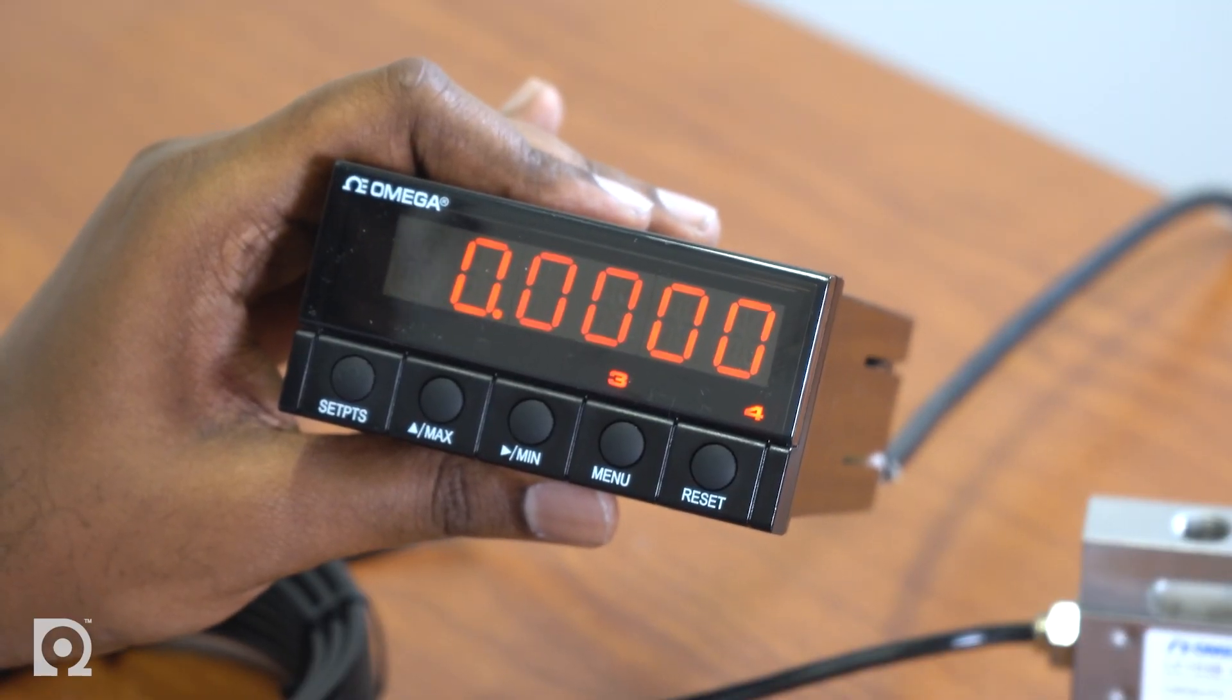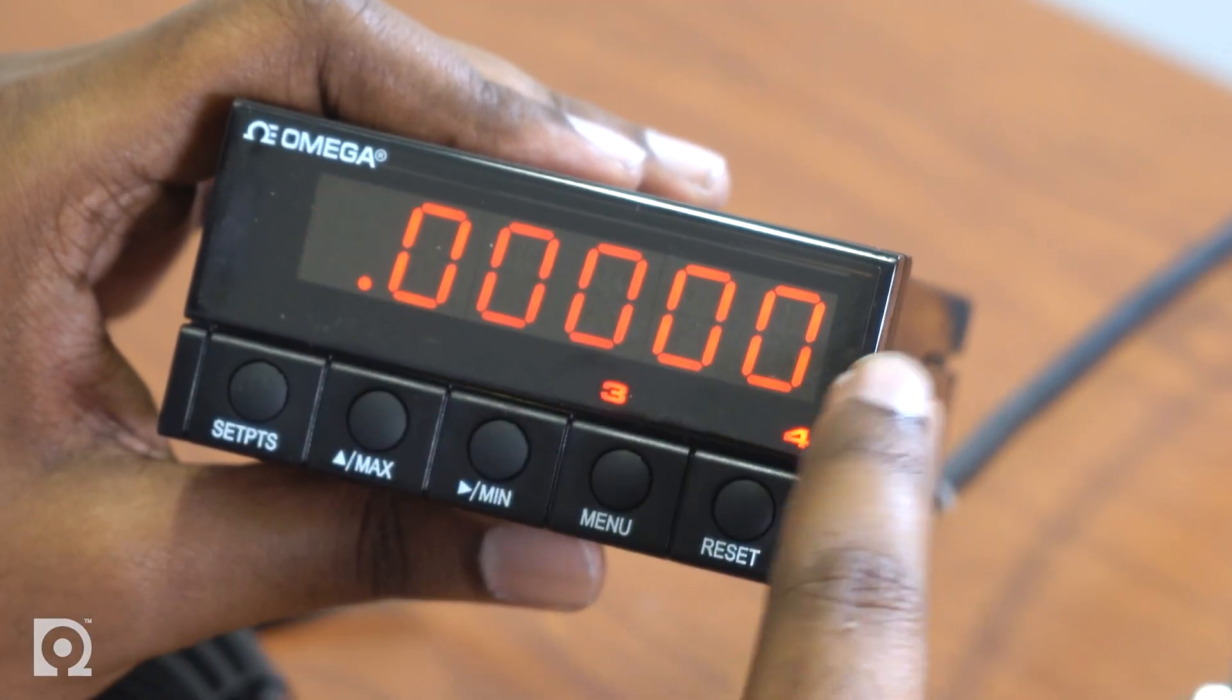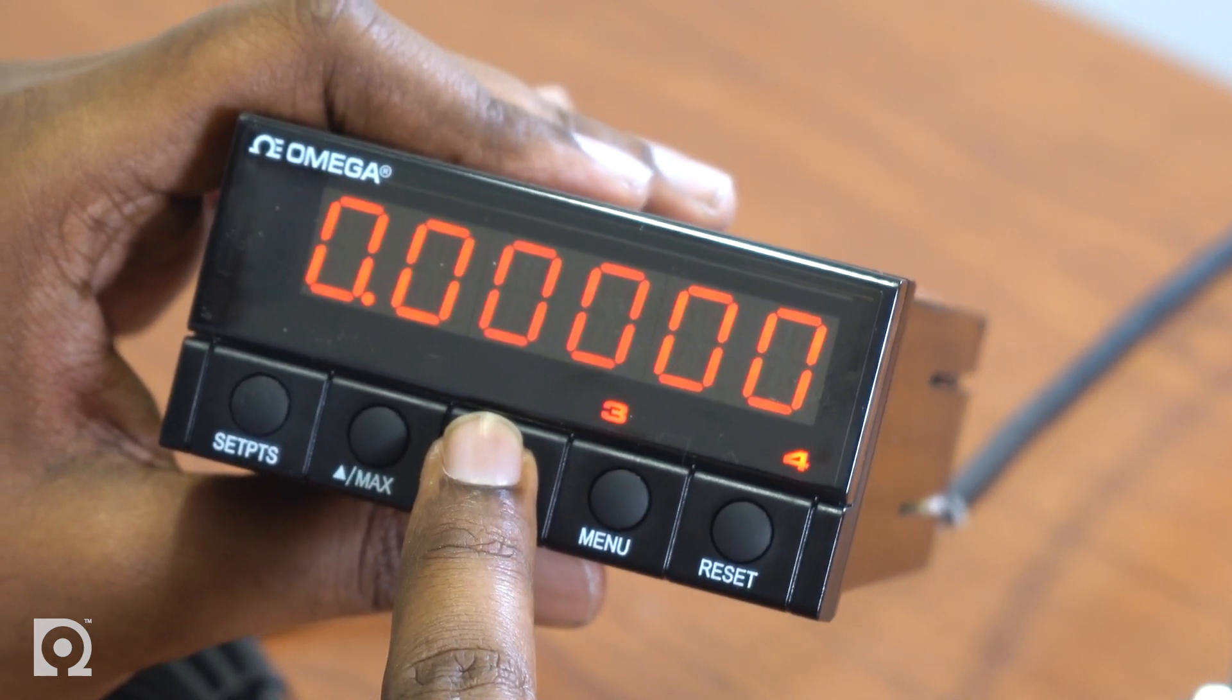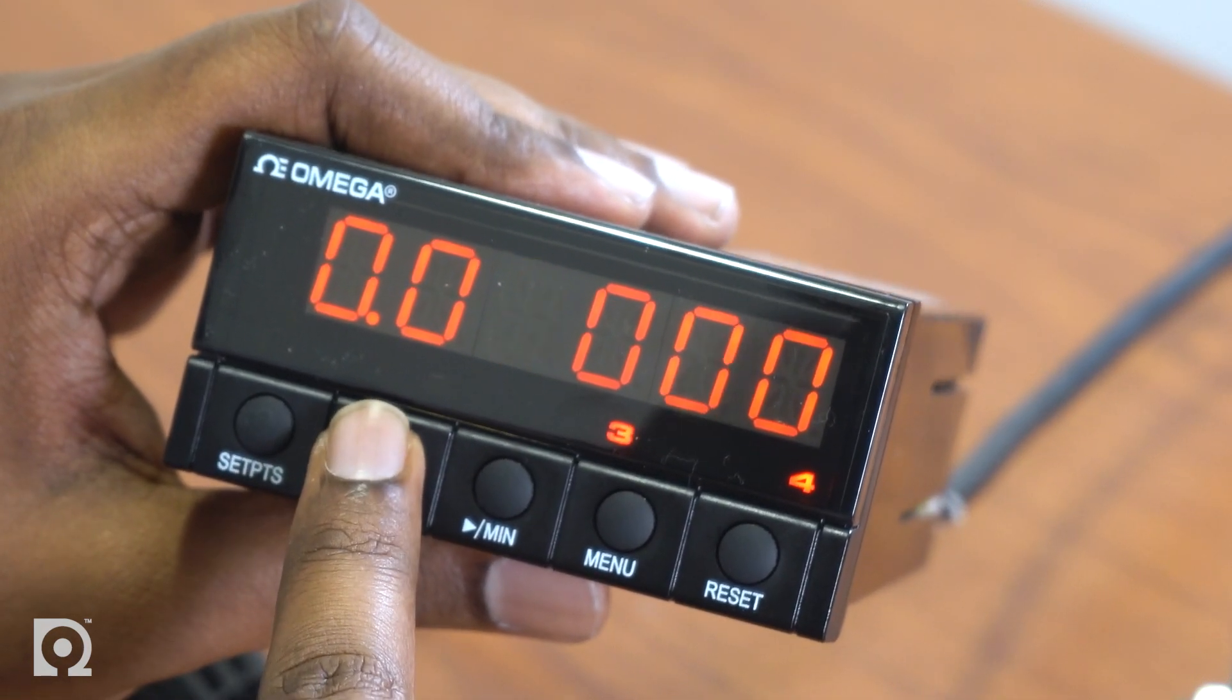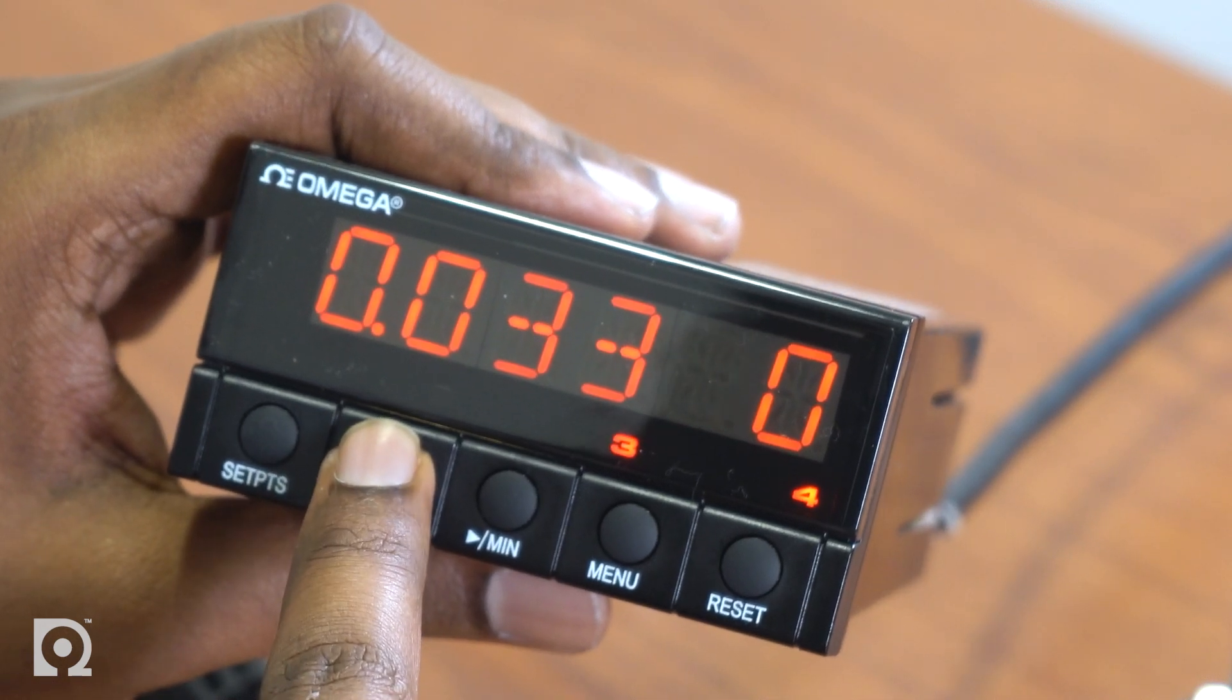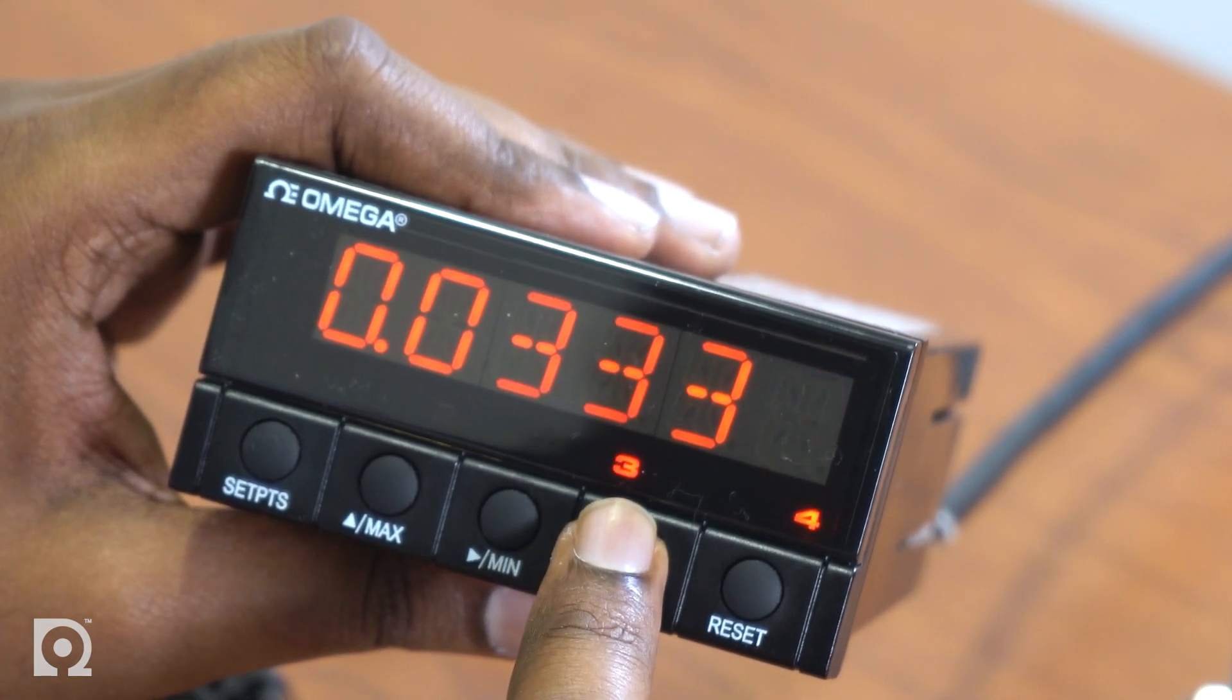To enter the RDG-SC, press the min button once, and you'll see whatever value was set by default when it shipped to you. So this value should be entered with the value that you calculated. In this instance, it's 0.03333. In order to change this value, you can use the min and the max key. The min key basically scrolls through the value of the digits, and the max button changes the value of the digits. So I'm going to go ahead and set the value to 0.0333. Once you've set this value to whatever you calculated this value to be, press the menu button once.